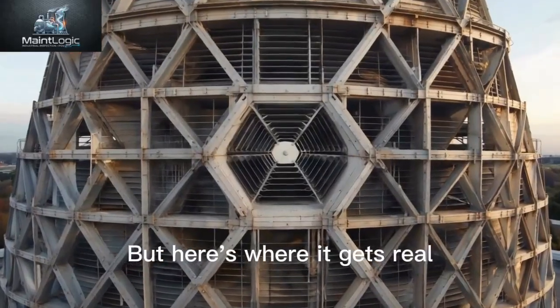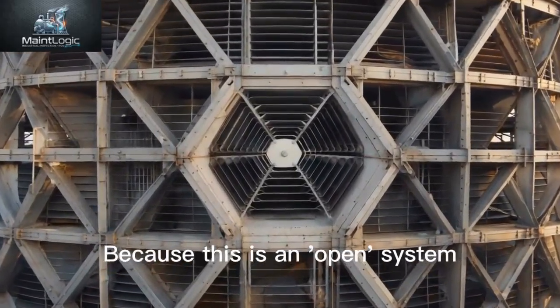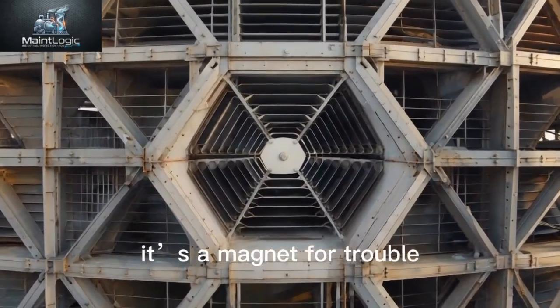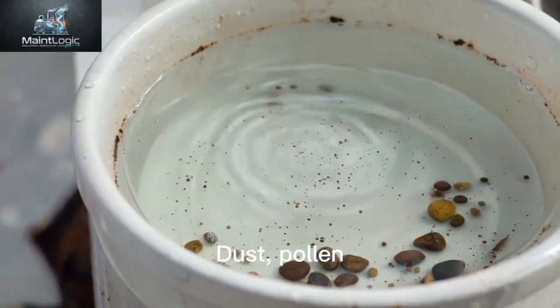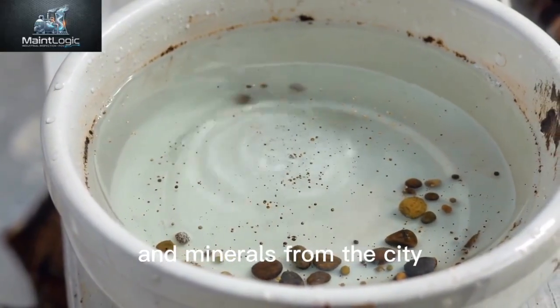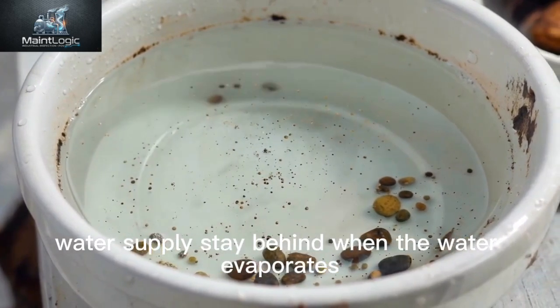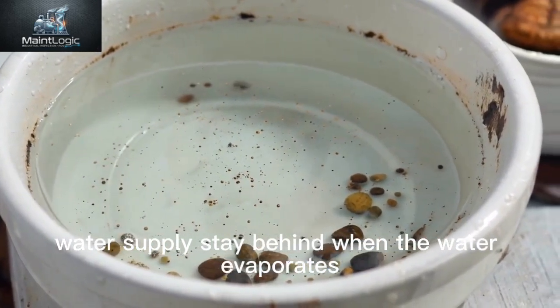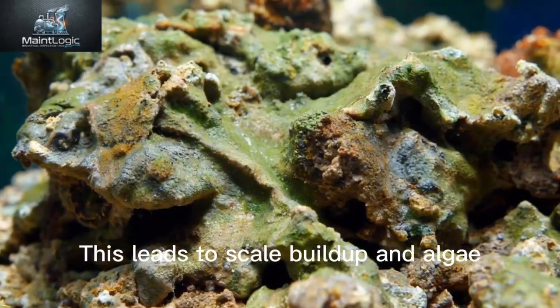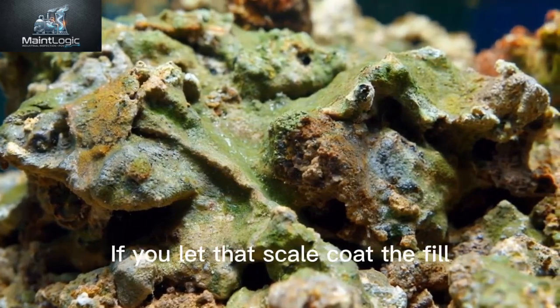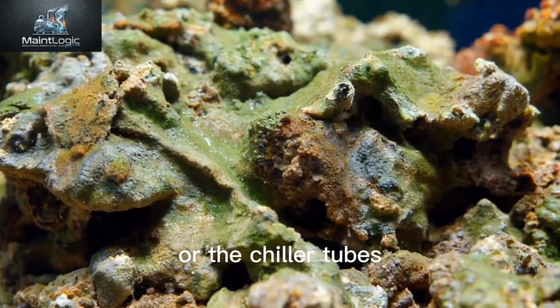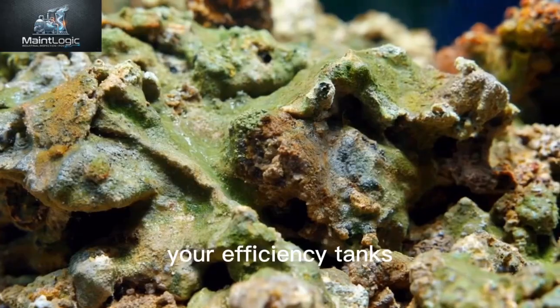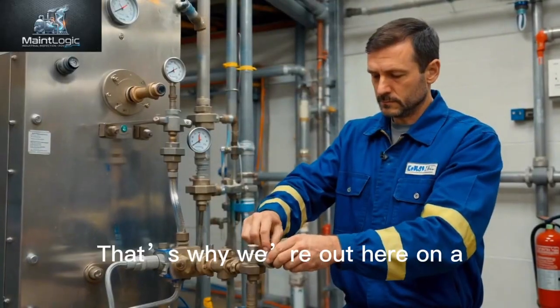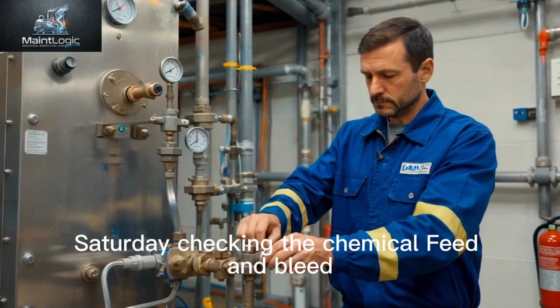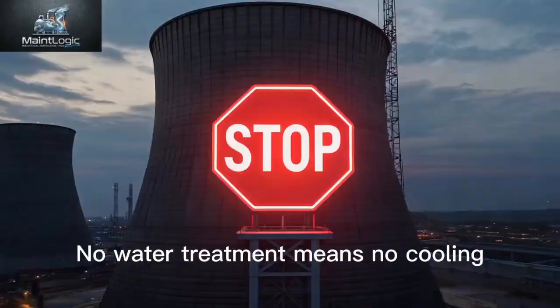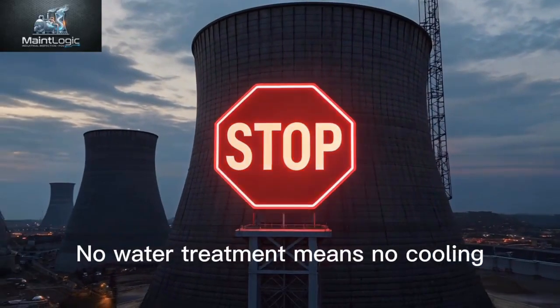But here's where it gets real. Because this is an open system, it's a magnet for trouble. Dust, pollen, and minerals from the city water supply stay behind when the water evaporates. This leads to scale buildup and algae. If you let that scale coat the fill or the chiller tubes, your efficiency tanks. That's why we're out here on a Saturday checking the chemical feed and bleed. No water treatment means no cooling.